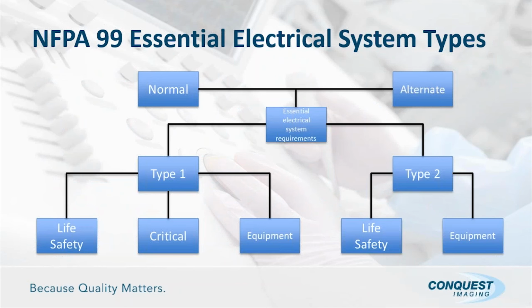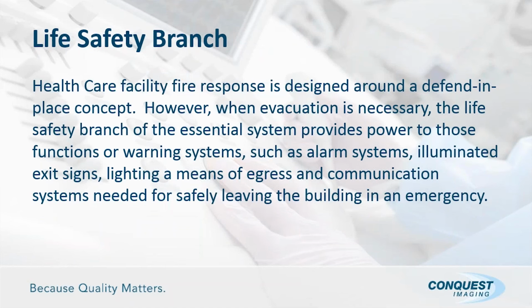You have normal and alternative power supplies supplying the essential electrical systems. Type 1, you have the 3 channels. You have the life safety, the critical, and the equipment branch, whereas in type 2, you only have the life safety and equipment branch associated with it. So those are the different branches that you're associated with. And let's define each one of the branches. The life safety branch, NFPA defines as healthcare facility fire response is designed around a defend in place concept. However, if evacuation is necessary, the safety branch of the essential system provides power to those functions or warning systems such as alarm systems, illuminated exit signs, lighting as a means of egress, and communication systems needed for safely leaving the building in case of an emergency. So that's a life safety branch.